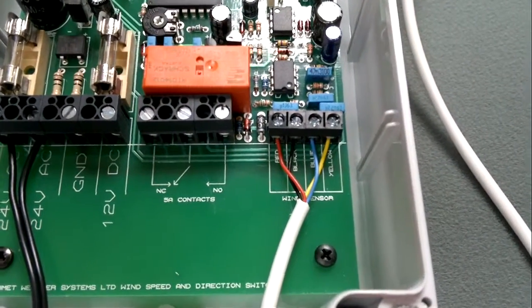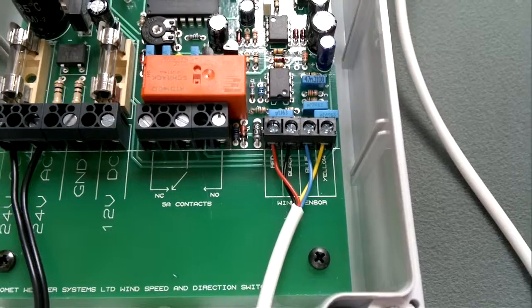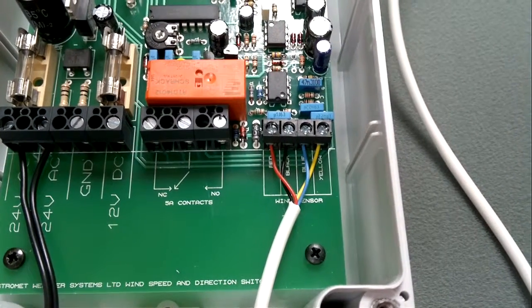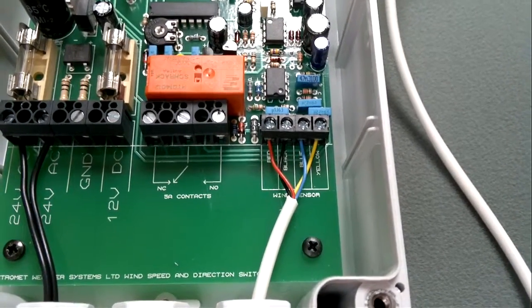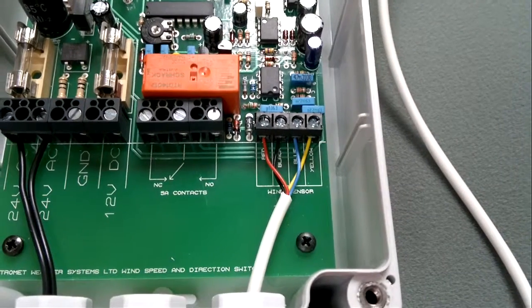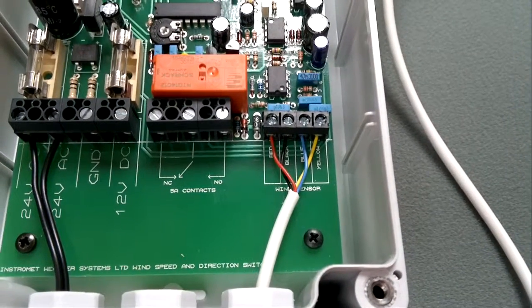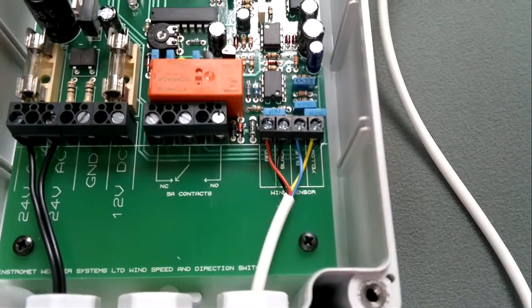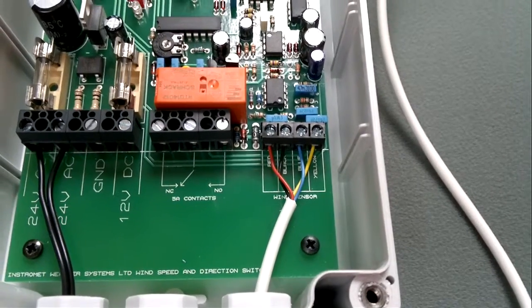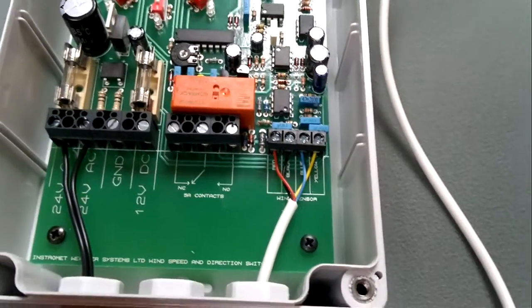And then next to that is the connections for the wind sensor. So you see there red is the 5 volt power supply, black is the ground, blue is the signal coming in from the sensor for the wind speed and the yellow is the wind direction signal input.